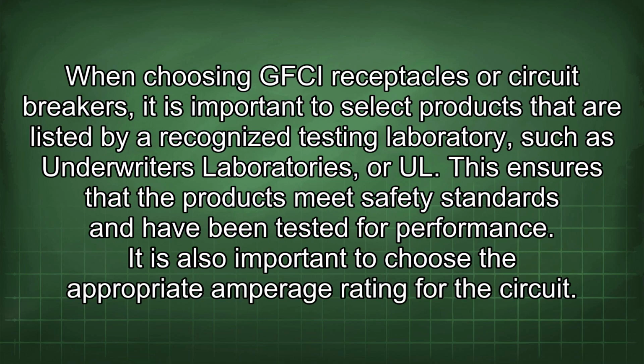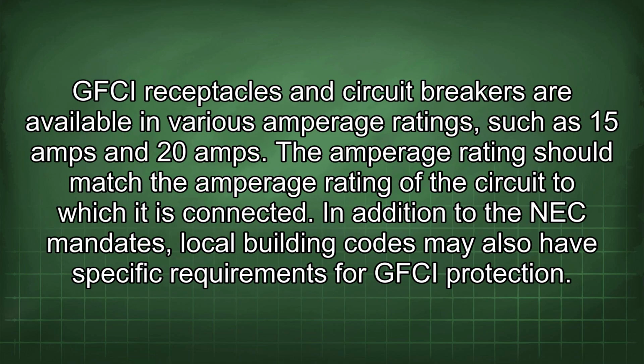When choosing GFCI receptacles or circuit breakers, it is important to select products that are listed by a recognized testing laboratory, such as Underwriters Laboratories, or UL. This ensures that the products meet safety standards and have been tested for performance. It is also important to choose the appropriate amperage rating for the circuit. GFCI receptacles and circuit breakers are available in various amperage ratings, such as 15 amps and 20 amps. The amperage rating should match the amperage rating of the circuit to which it is connected.